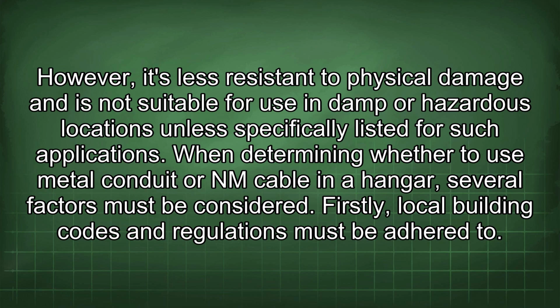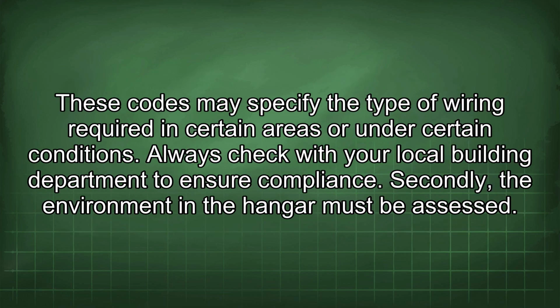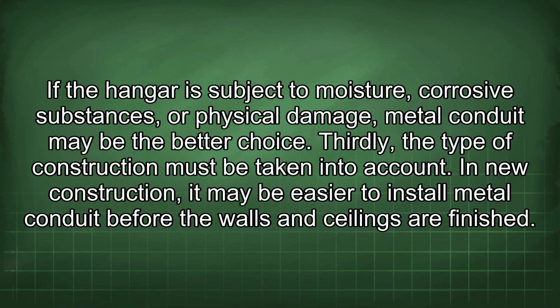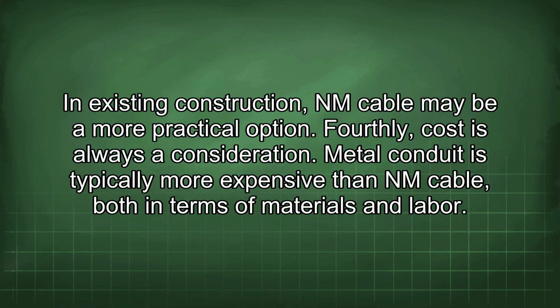However, it's less resistant to physical damage and is not suitable for use in damp or hazardous locations unless specifically listed for such applications. When determining whether to use metal conduit or NM cable in a hangar, several factors must be considered. Firstly, local building codes and regulations must be adhered to. These codes may specify the type of wiring required in certain areas or under certain conditions. Always check with your local building department to ensure compliance. Secondly, the environment in the hangar must be assessed. If the hangar is subject to moisture, corrosive substances, or physical damage, metal conduit may be the better choice. Thirdly, the type of construction must be taken into account. In new construction, it may be easier to install metal conduit before the walls and ceilings are finished. In existing construction, NM cable may be a more practical option.